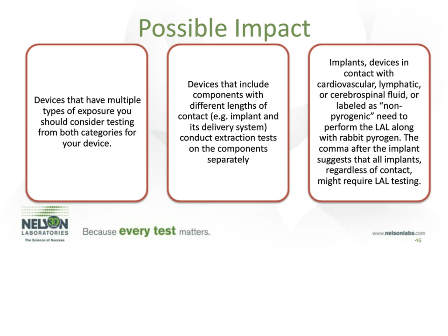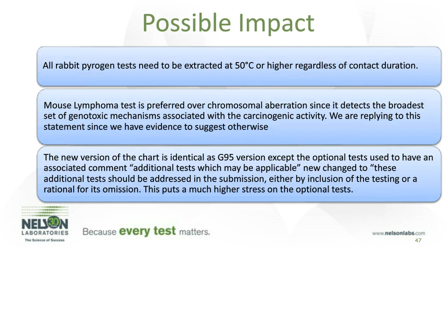And then the other one I want to talk about as far as possible impacts is that bottom one, which is the new chart. This is the chart right out of ISO, the new draft, and that's why the numbers down there are a little messy. I apologize, but this is right out of the draft. And if you can read it down there, we have circles, and those circles have always been possible tests that the FDA specifically, this is off the G95, may consider necessary, but were really looked at as testing that nobody did unless they had materials that the FDA were worried about.